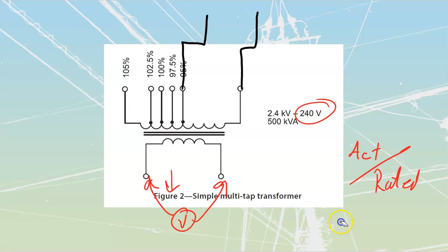But what I'm going to see is a boost. I won't be getting the full 240 out, but I'm going to be sitting a lot higher than this 220. We will calculate those ratios on the next one. But all it is, is a simple little bit of math where you say, what is it rated at? What am I at? I'm going to move this because if I'm getting 95%, then I move it down to the 95% voltage tap, which will bring this up.